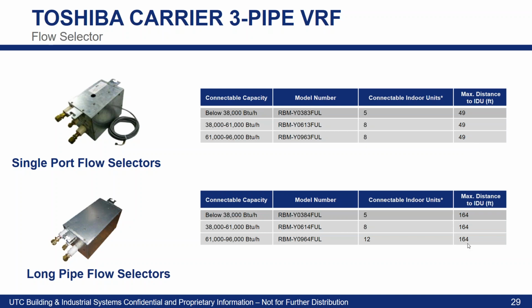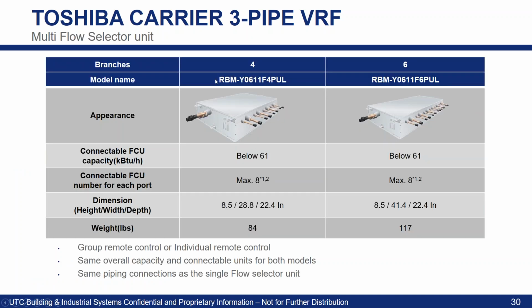Max distance 49, max distance you can see 164, obviously for the long pipe flow selectors. Next slide. TOSHIBA-Carrier, we go up to 4 and 6 with being our max flow selector option. Now, as you might be asking yourself, you've seen branch controllers with probably up to 16, 18 ports. Toshiba's mindset with this is that we more want redundancy from a flow selector standpoint. So if you can imagine, you've got a whole wing of a building that's being served by a 16 or 18 port box. If there's any issues with that box, you're going to lose that whole wing. While TOSHIBA-Carrier's mindset is break it up. If you do have any issues with the flow selector, you're not going to lose that entire wing. So that's the whole mindset there, guys.